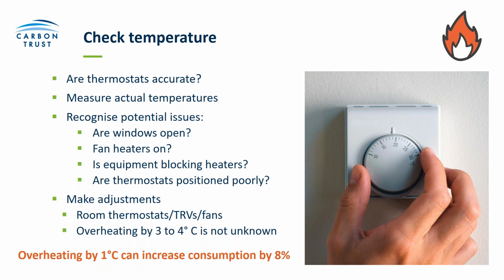Then make your adjustments—you can have different thermostats for different rooms, and install radiator valves so different radiators can be heated to different temperatures. The statistic here shows that overheating by 1 degree centigrade can increase consumption by 8%, a big potential energy saving. Overheating by 3 to 4 degrees is not uncommon, which is a huge increase in consumption if your offices are overheated.